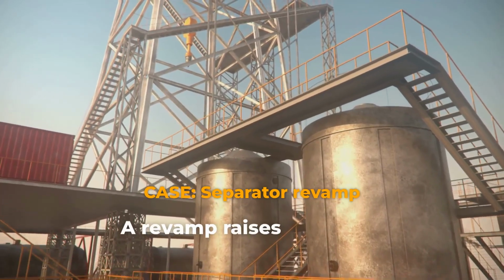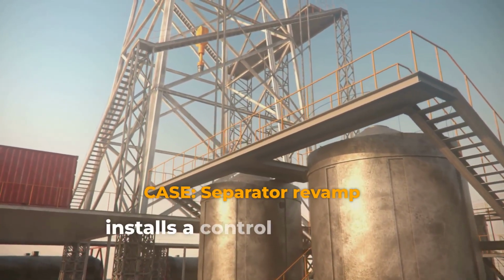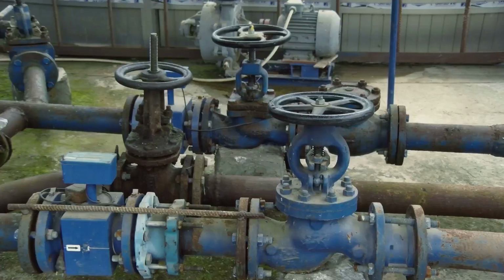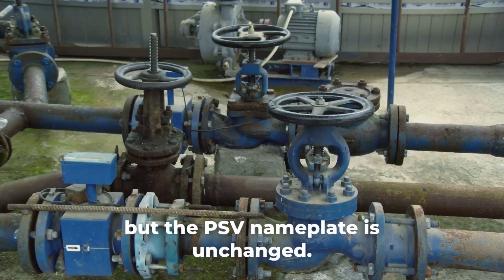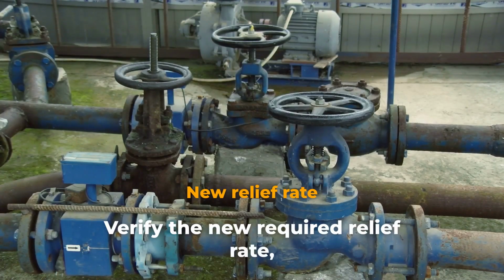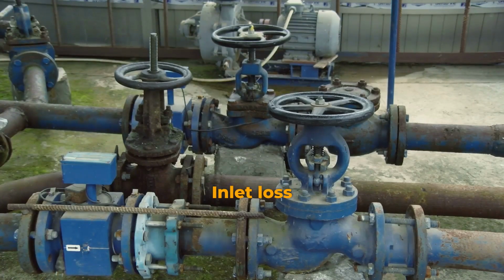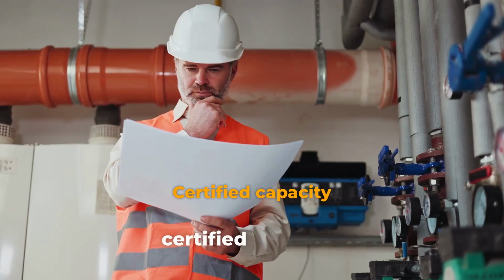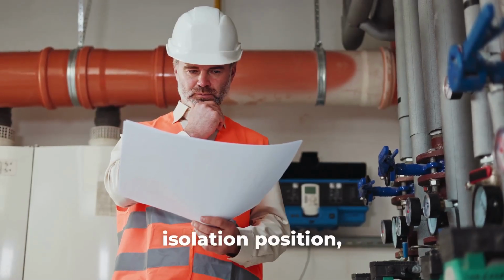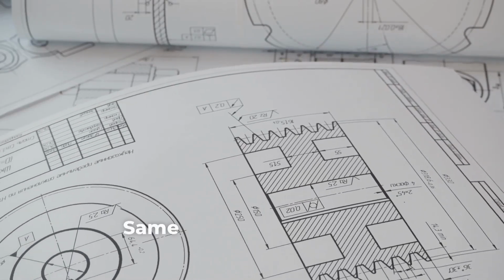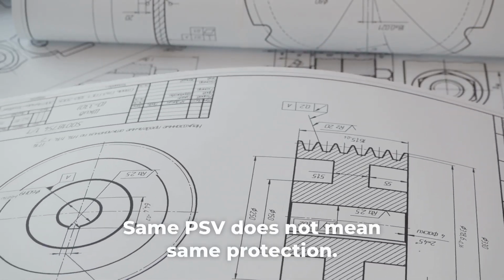A revamp raises upstream pressure and installs a control valve with a larger Cv, but the PSV nameplate is unchanged. Verify the new required relief rate, actual relieving properties, inlet loss, back pressure, flare header simultaneous loads, certified capacity, isolation position, and inspection history. Same PSV does not mean same protection.